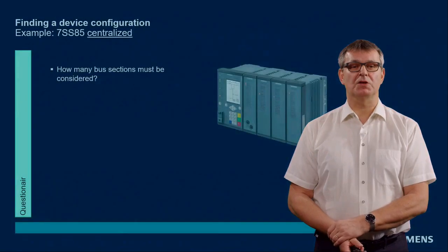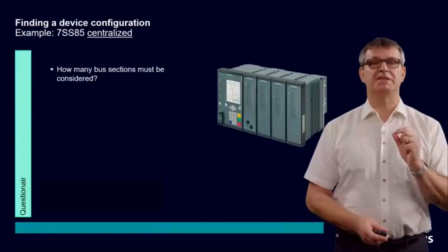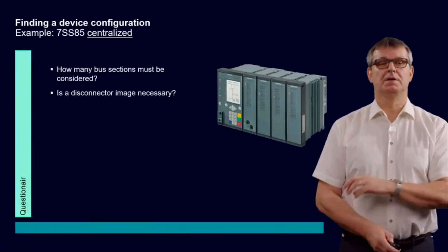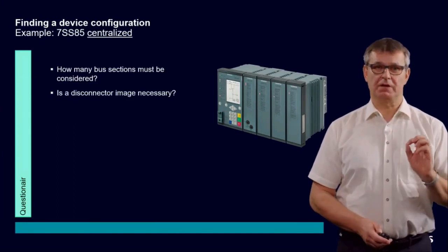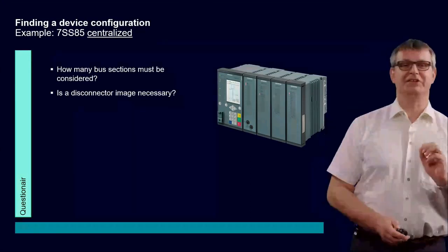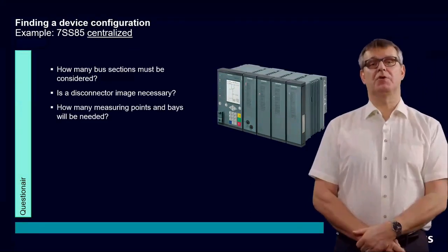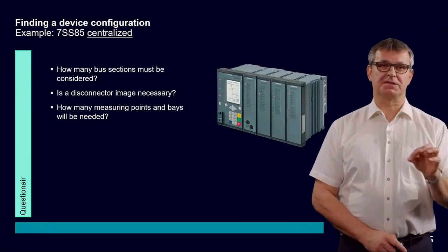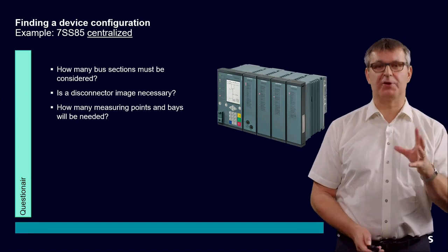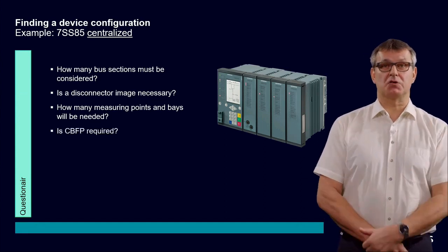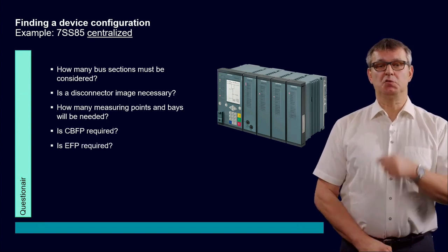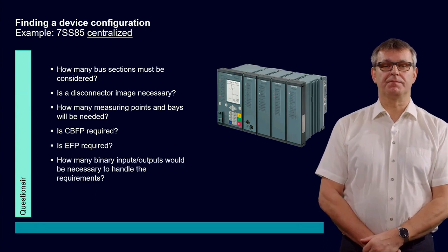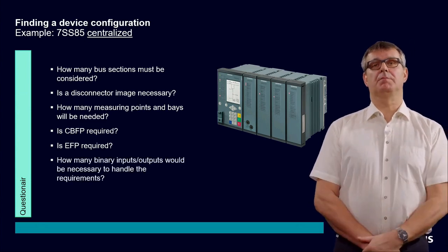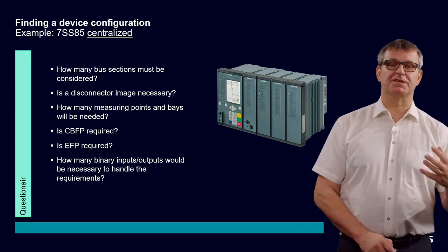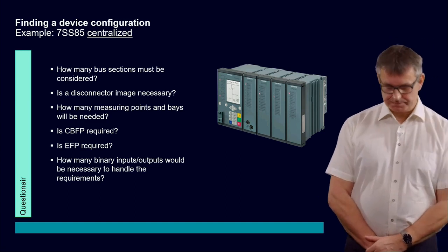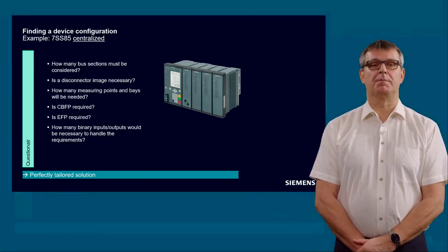What questions have to be answered? How many bus sections must be considered? Is a disconnector image necessary? I will explain it later in detail. How many measuring points and how many bays? This is quite often similar, but can quite often also be different. Do we need a circuit breaker failure protection? Do we need end-fault protection? And how many binary inputs, binary outputs are necessary to handle the whole configuration? Let's start with the bus sections.